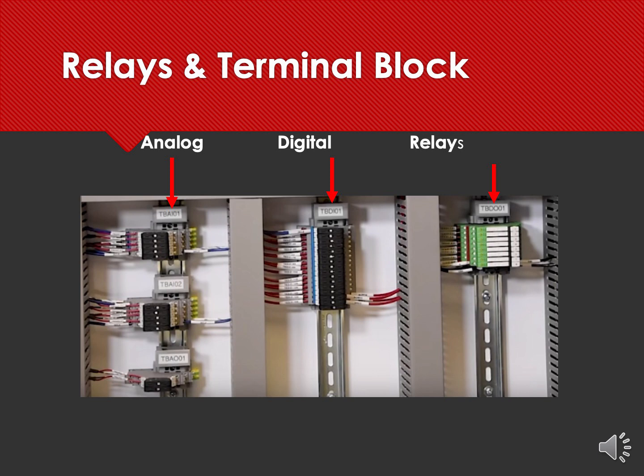In the middle tier here, we have the TBD, which is the digital part of the panel. So the digital, of course, is more the on-off part of the system, so it controls things like switches. And on the far right side are the relays for the panel itself, and these can be everything from motor starting relays to whatever it is that we're controlling with the panel itself. So this is where all of the controlled AC and DC systems, in this case the DC systems, come together, and they're distributed out to the equipment that is controlled by the industrial control panel. So let's go to the next slide.